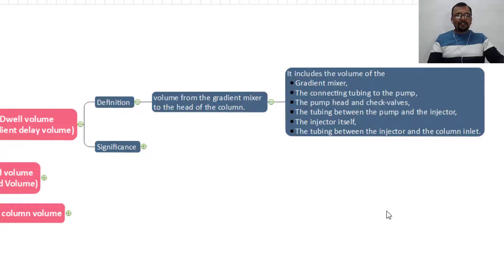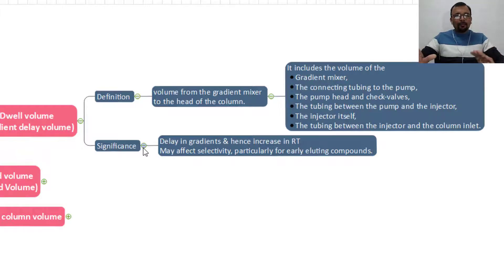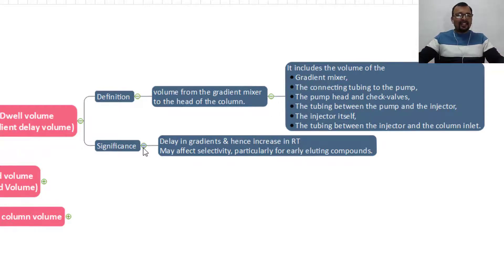Let us also understand the significance of the dwell volume and why it is so important. As you know, dwell volume is also known as the gradient delay volume. The higher the dwell volume, the more the gradient will be delayed during the HPLC run, and that is what causes a delay in the gradient.